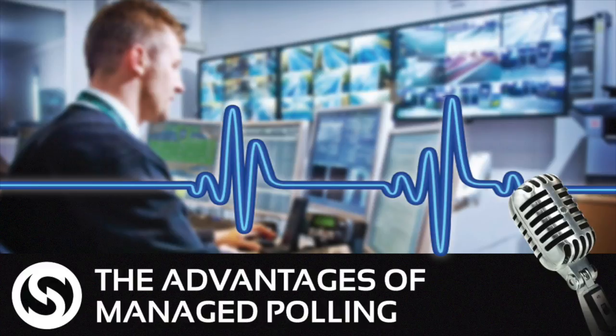But I think that's where the misconceptions come into it, is that everybody has taken the fault recognition time as the polling time. So like what Carl said, if the Australian standard states that this class of monitoring must have a 1 hour fault recognition time, they interpret that as we must poll that device every hour. And what they're doing is not allowing them enough time to analyze or ensure that it's actually lost communication or just a lost data packet.